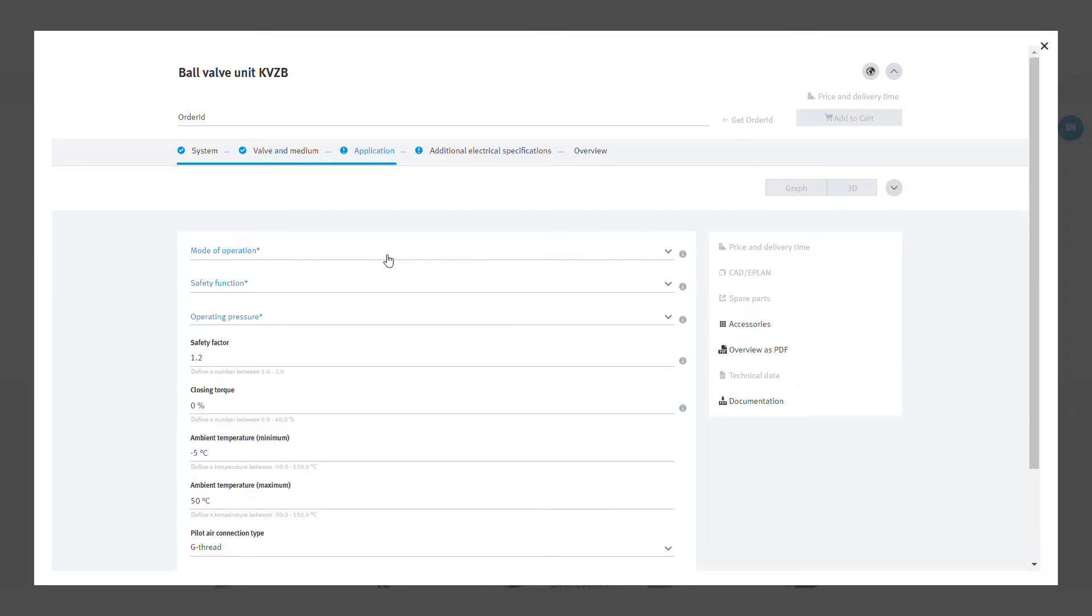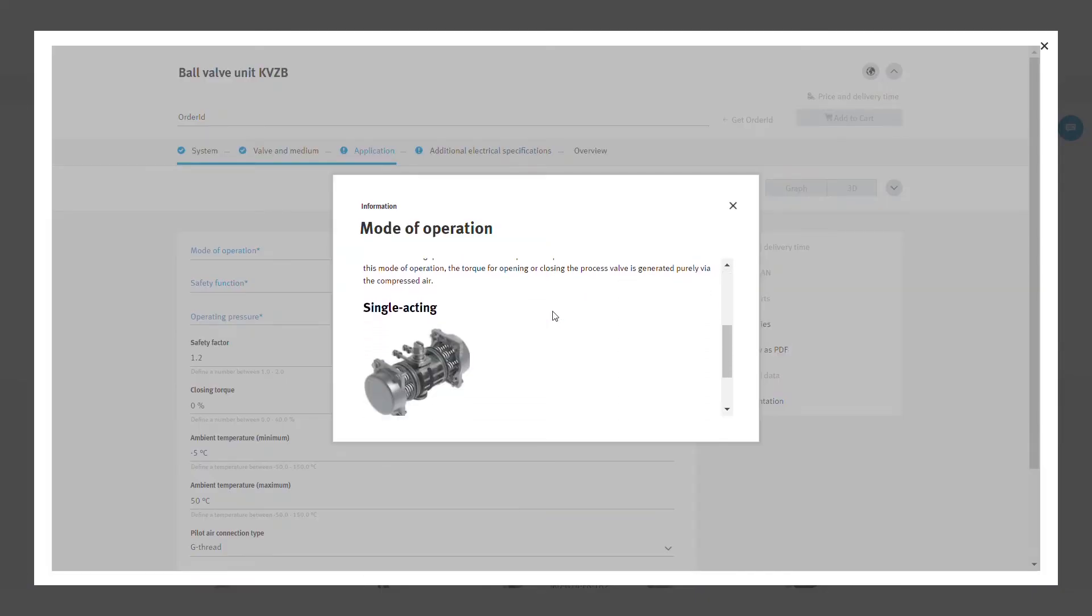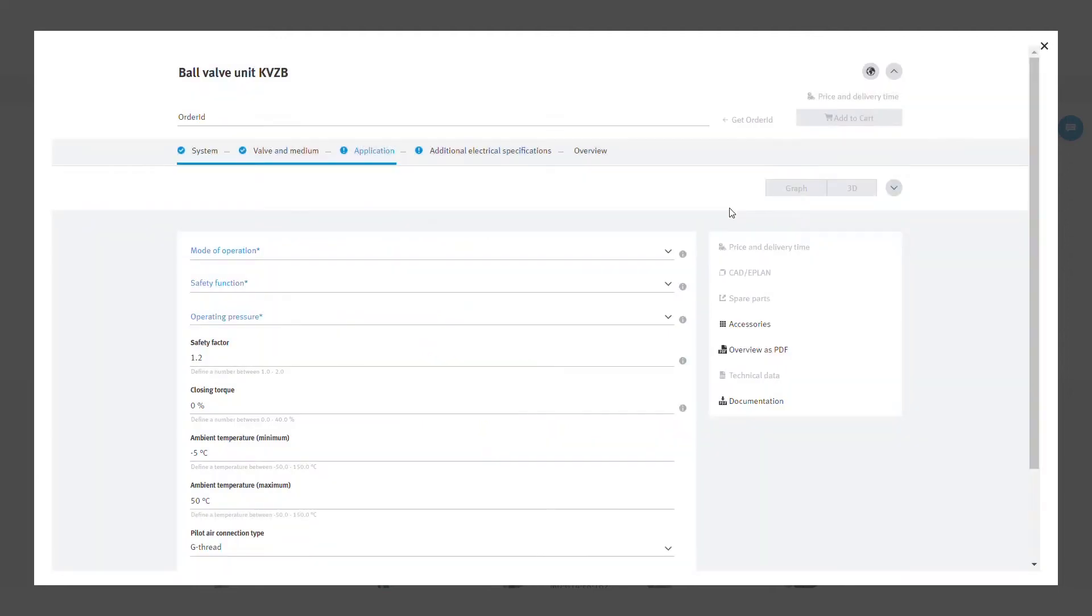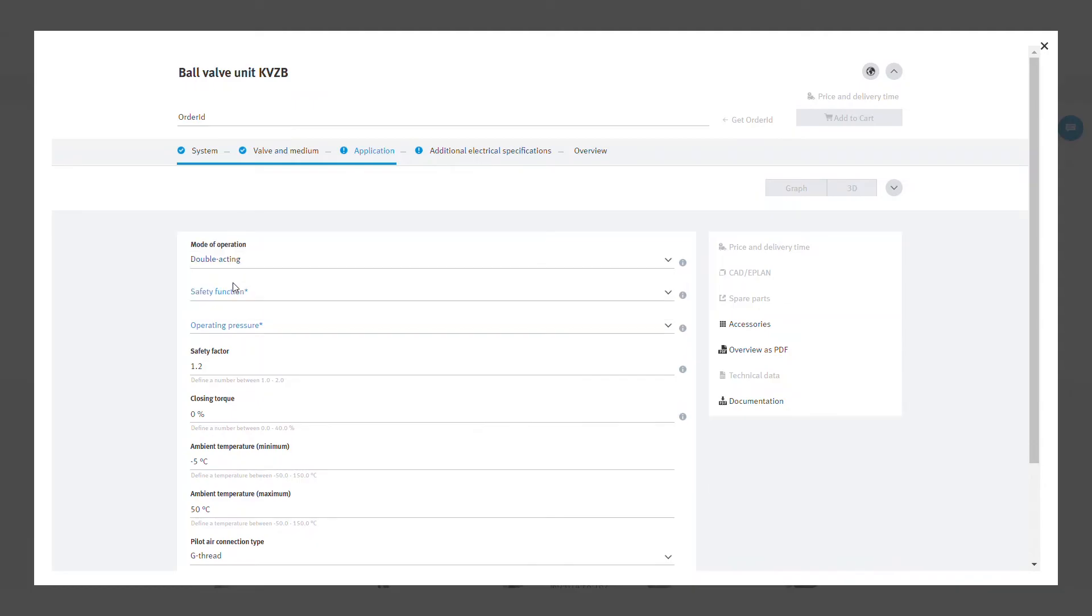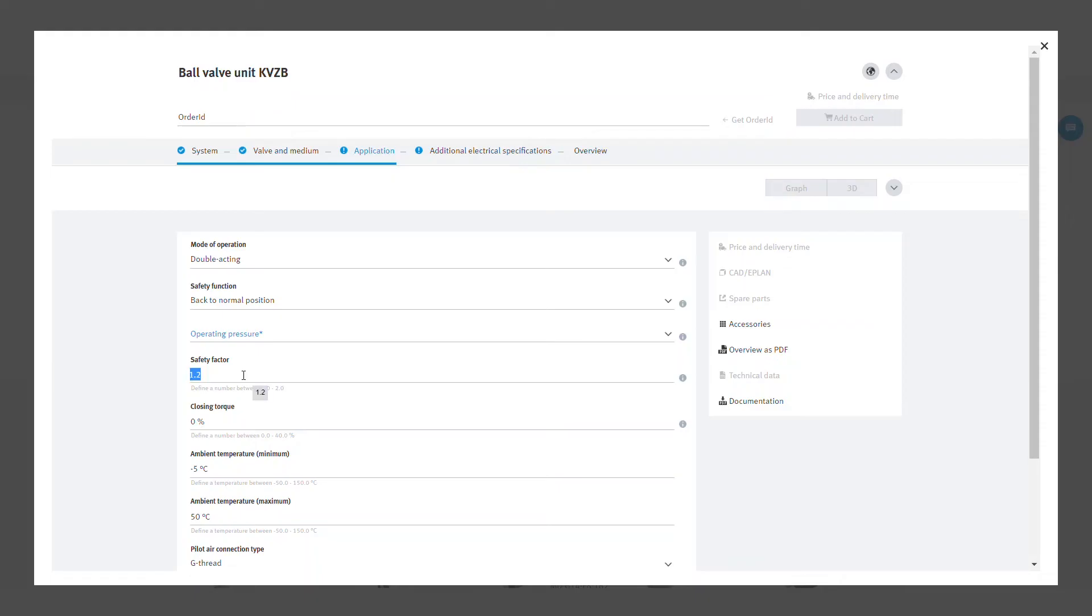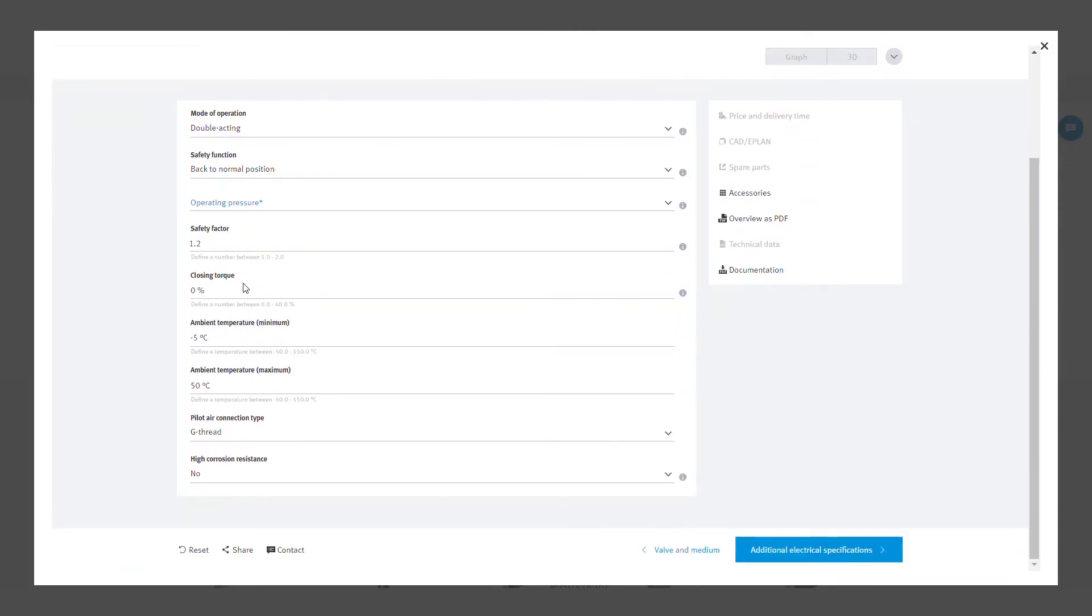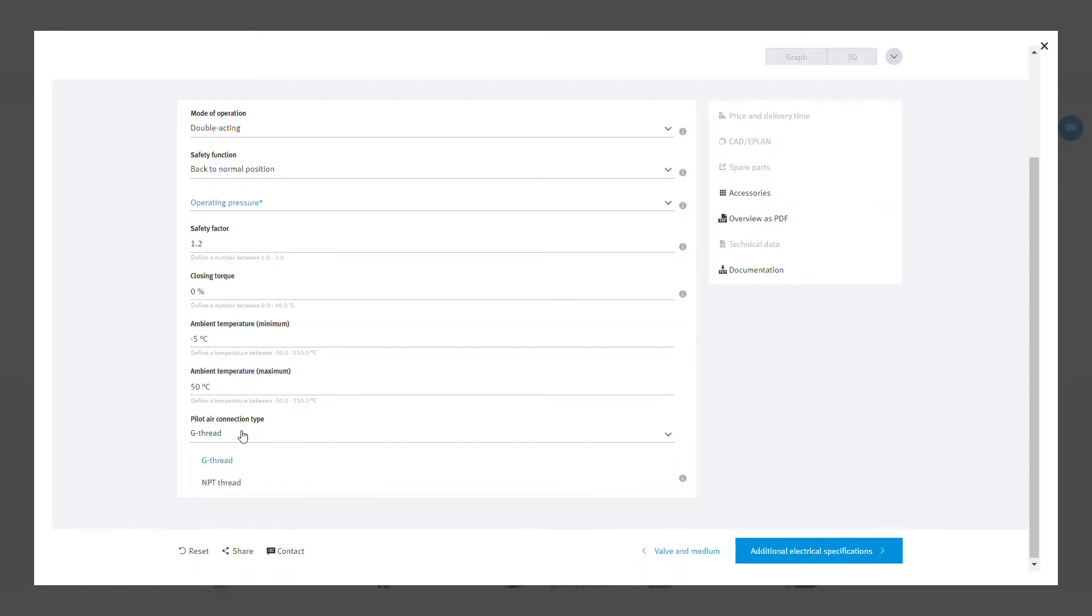Application refers to the quarter turn actuator. Click on the information button for more details and explanation. You can select the mode of operation. You can change the safety factor to increase the torque reserve available. Then add the minimum and maximum ambient temperature according to your process. You can select the pilot air connection type and high corrosion resistance. By selecting yes, the quarter turn actuator will have an epoxy coating and stainless steel shaft.